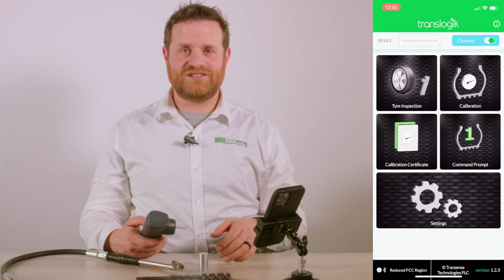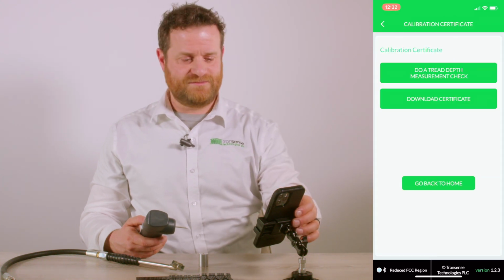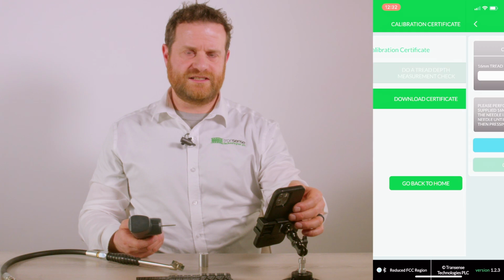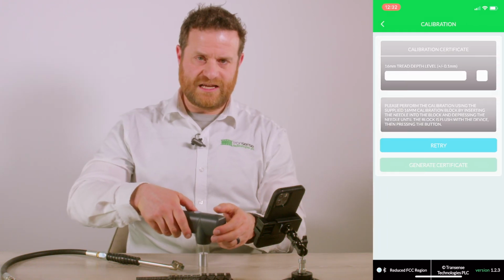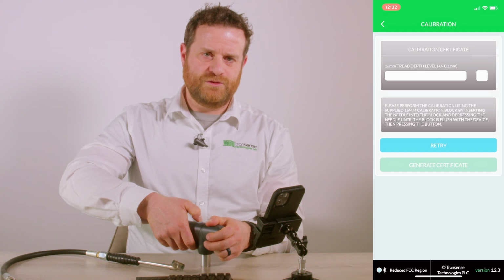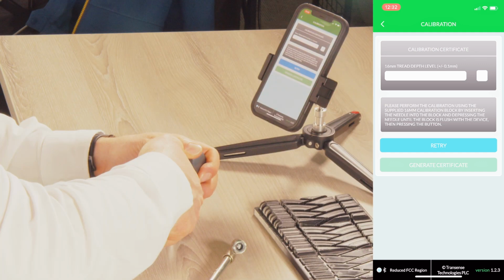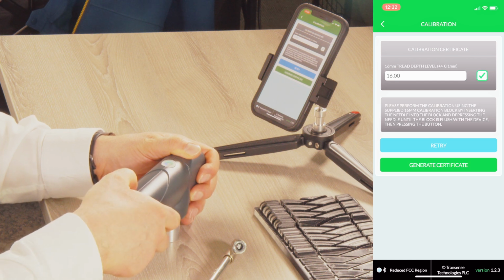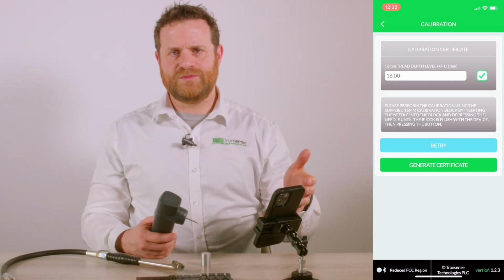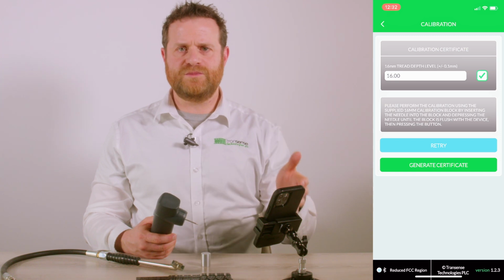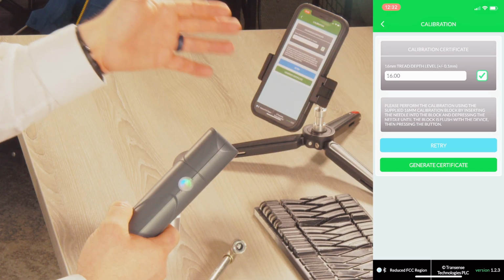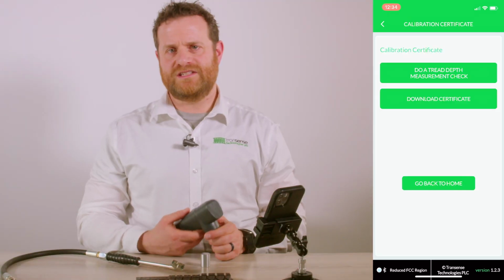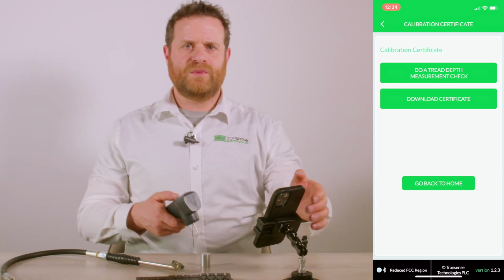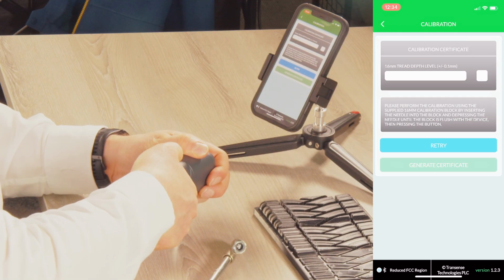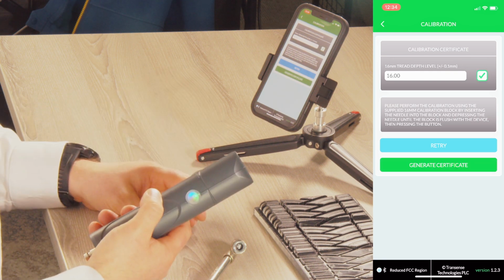To produce a calibration certificate, select Calibration Certificate. First, perform a tread depth measurement using the 16 mm depth hole. Press the tool firmly against the block, then press the multifunction button. A measurement will be recorded, and if the measurement is within the allowed range, a green tick will appear. If the measurement is out of range, a message will be displayed, and the measurement will need to be remade by pressing the retry button and following the previous instructions again.